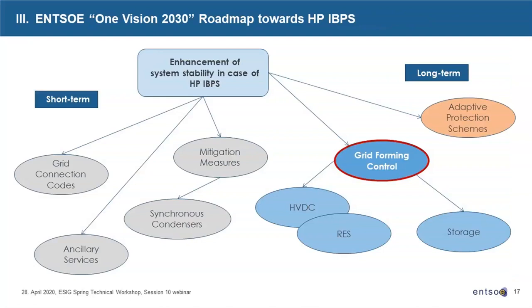In the short term, you have to find operational solutions, using available technologies to mitigate, for example, the loss of inertia by synchronous condensers, as this is available technology. You can at times adjust or tweak grid connection code requirements, and establish new market products, ancillary services for fast frequency responses, and so on. And on the longer term, you need to think about new technologies to come in, and new and sustainable solutions to be found, established and defined.